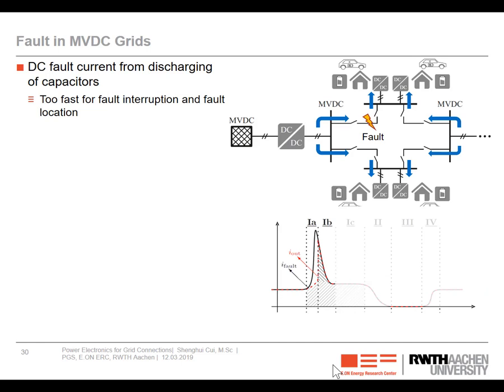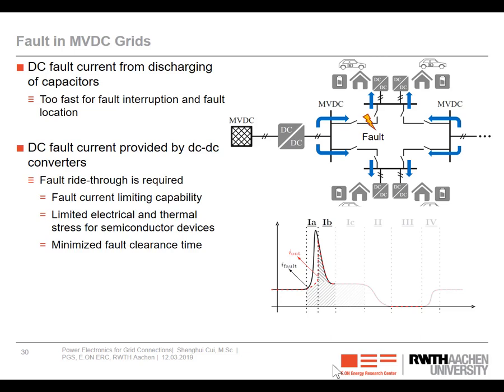And as long as the capacitor is fully discharged, the device DC link current is exactly equal to the fault current. Then from this time, we need to do something to clear the fault current. So how can we do it? To do so, we need these DC-DC converters to have the so-called fault ride-through capability, whereby we can limit and extinguish the fault current in an active manner.